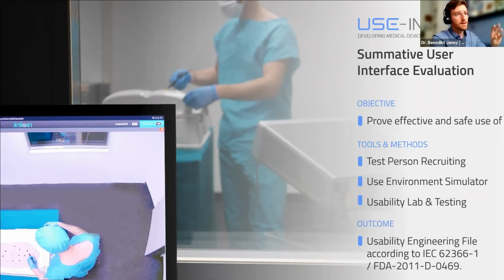The FDA, the US FDA is special. For example, the FDA requires you to test with US citizens, but all of them require to recruit representative users. So really medical professionals that have experience in the field. Make sure that you simulate the user environment if necessary. And a lot of times you have to use usability lab facilities.